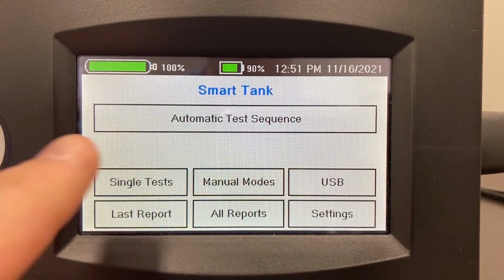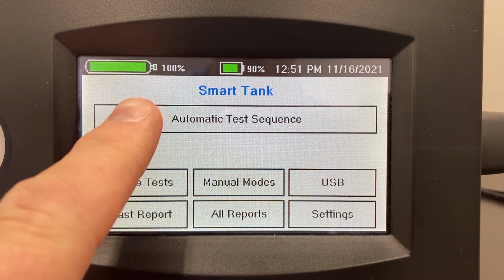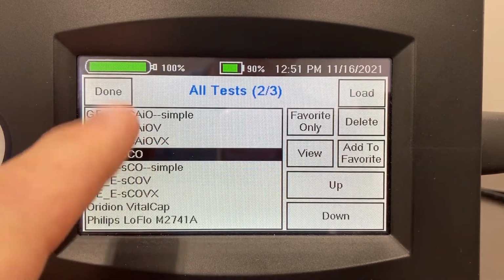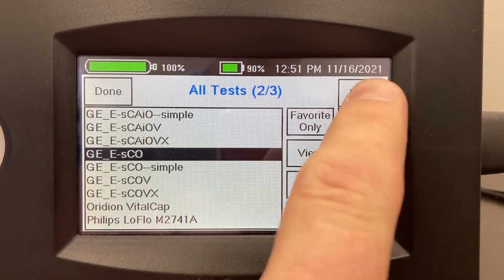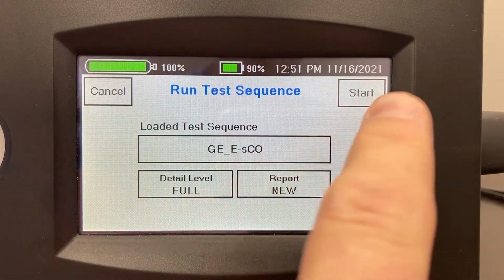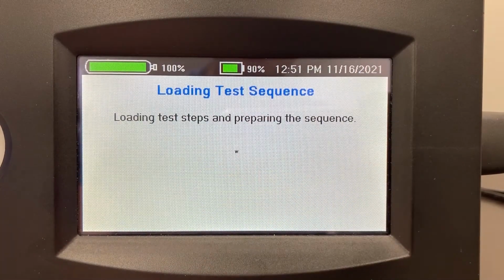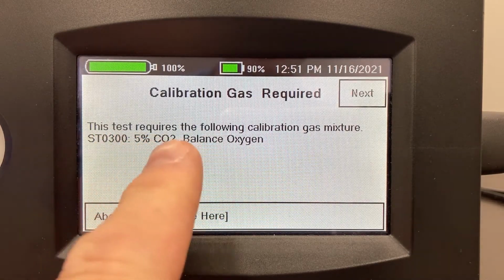All right, to run the test sequence, we start by touching automatic test sequence. Make sure we've selected the right test sequence and press load, and then start. This tells us what gas we should be using.